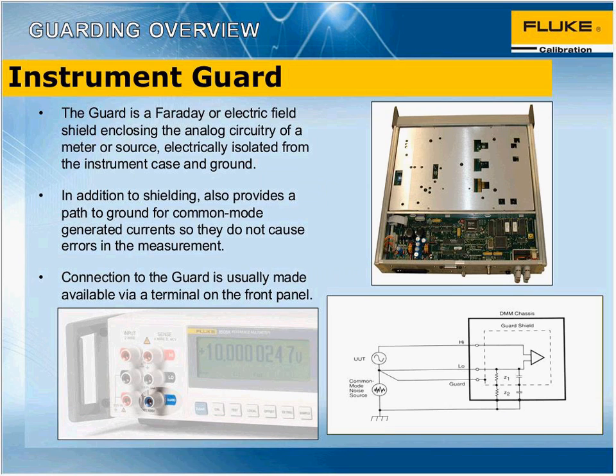a Faraday shield, and you can see the picture of the instrument there in the diagram below, representing a shield that's surrounding all of the sensitive measurement circuits to avoid problems from electrostatically coupled or electric field coupling. And as I said, if we use mu metal as well, we can do a good job of shielding from magnetic effects. But there's an effect where it helps dramatically, and that's in what we call common mode.